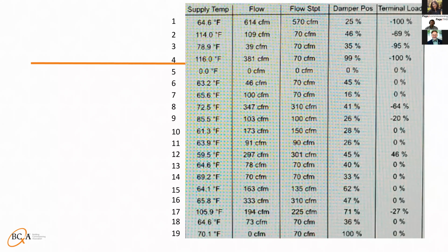And last but not least, number 19, the damper is 100% open, but no flow. Maybe the tubes to the flow cross were disconnected. Maybe the T-caps have degraded and fallen off. Maybe there's a zeroing problem. Maybe the transducer is bad. So before we tested or commanded anything, we may have already discovered 3 issues.